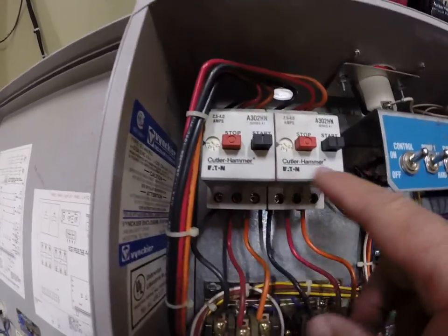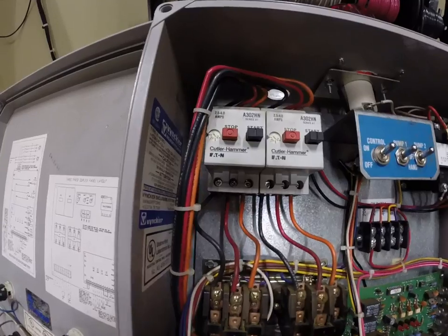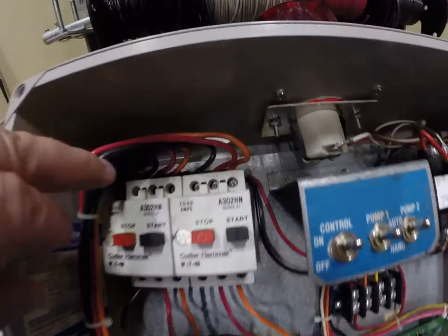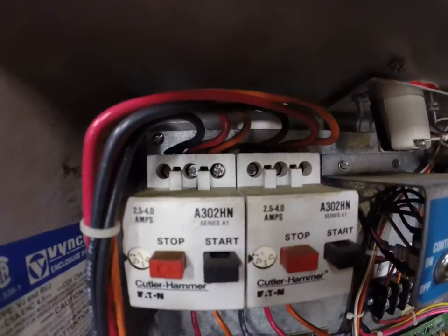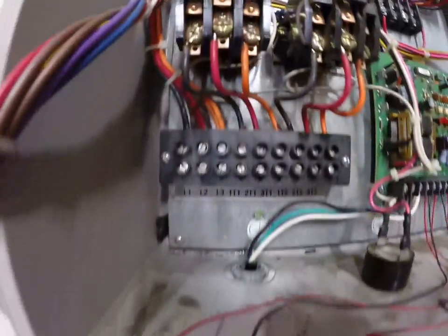This is a motor contactor, another motor contactor. You might see the familiarity of when I took apart the NEMA starter—it had these contacts that were closed. Here you actually see the components closing. This is the actual motor starter itself. This goes with this contactor. You've got your three-phase feeds coming into the top, your L1, L2, L3. Come out the bottom, T1, T2, T3, which stands for your load. Those loads power up these contactors.